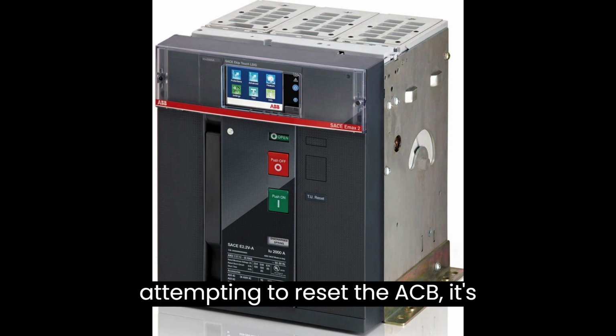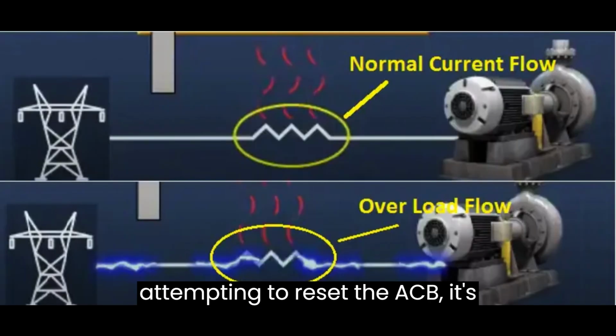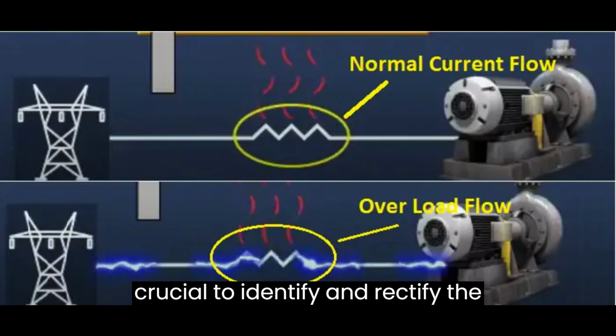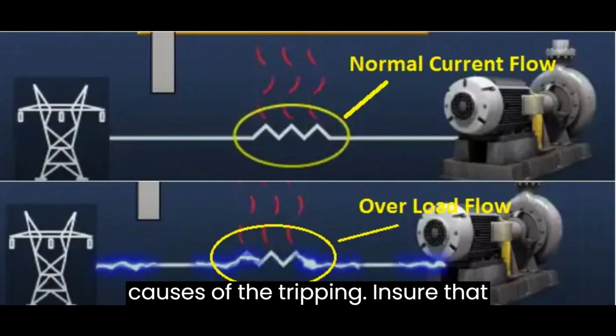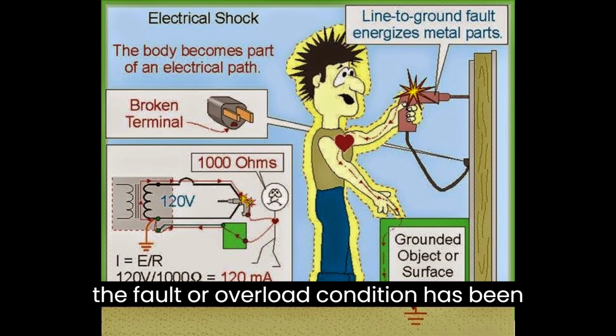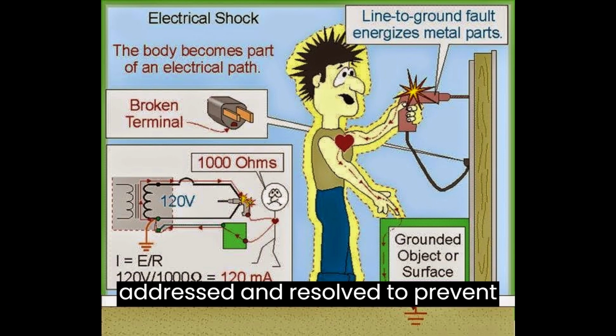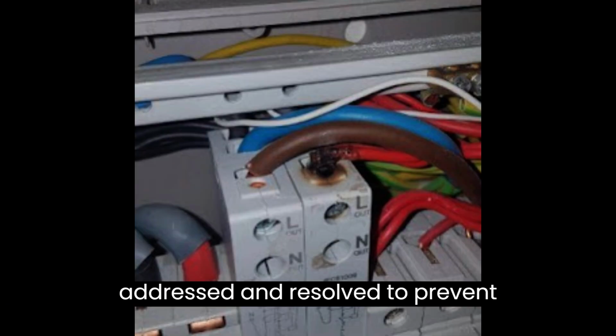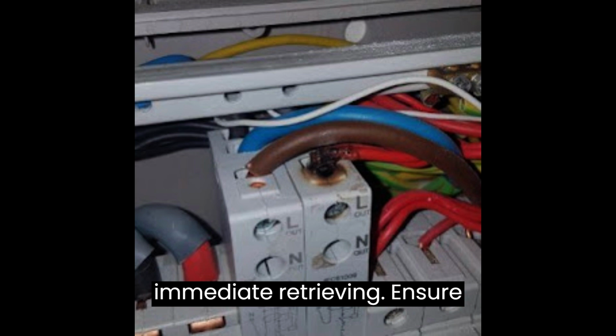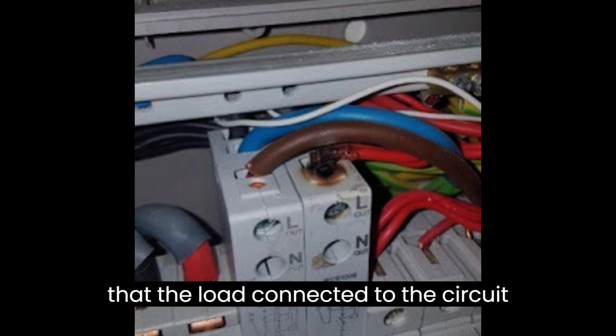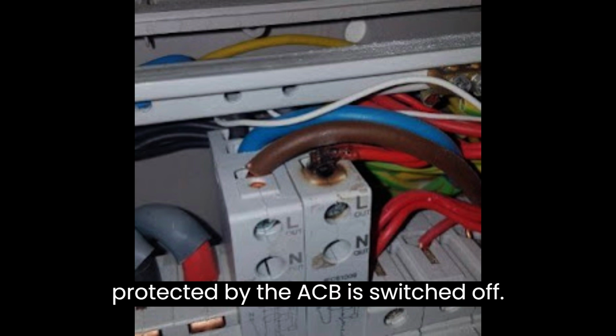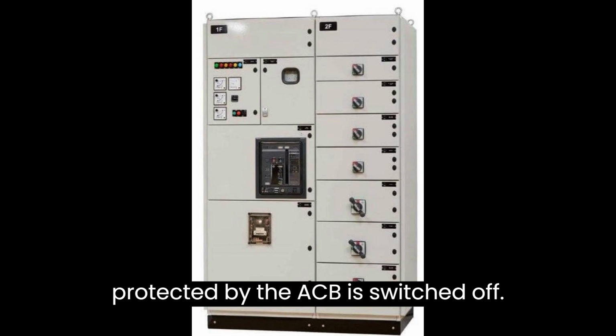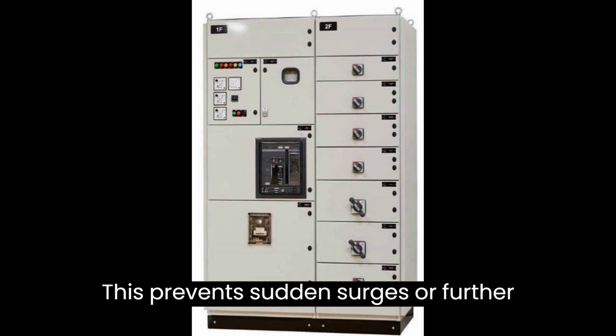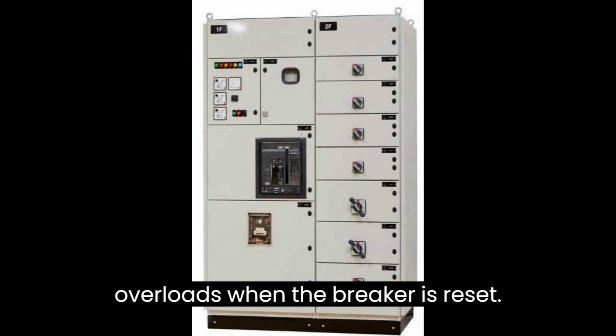Before attempting to reset the ACB, it's crucial to identify and rectify the cause of the tripping. Ensure that the fault or overload condition has been addressed and resolved to prevent immediate retripping. Ensure that the load connected to the circuit protected by the ACB is switched off. This prevents sudden surges or further overloads when the breaker is reset.